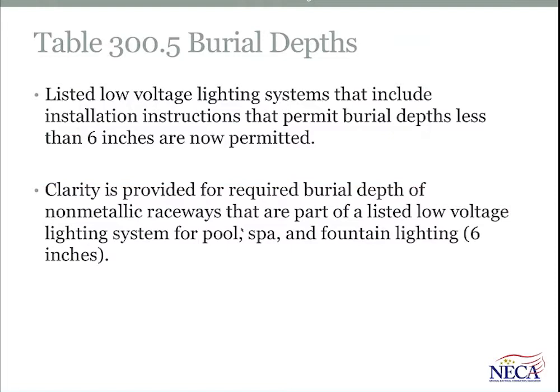Table 300.5, as everyone knows, is the table we lean on for minimum burial depth requirements for the various wiring methods we install. And there was a conflict that happened in the last couple of cycles between the manufacturer's instructions for listed low voltage lighting systems and what was required by the table, 300.5.